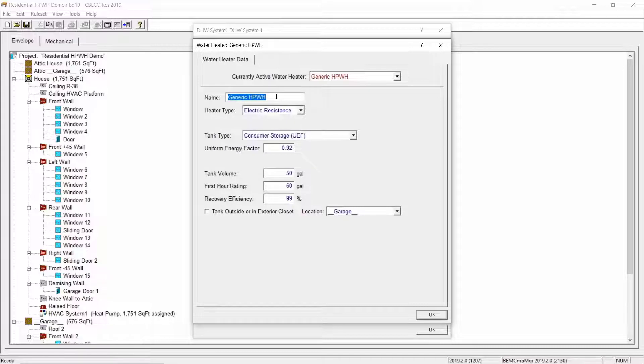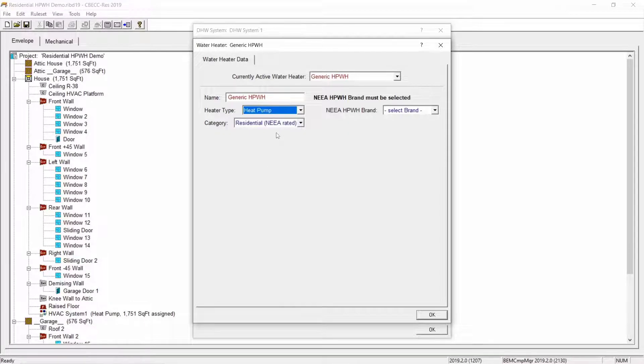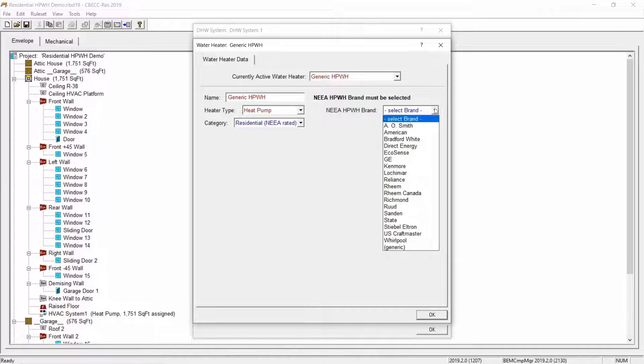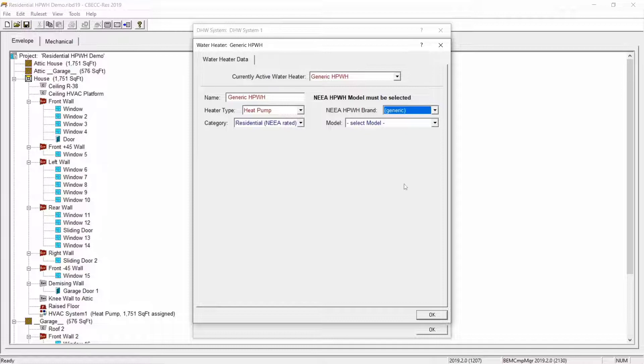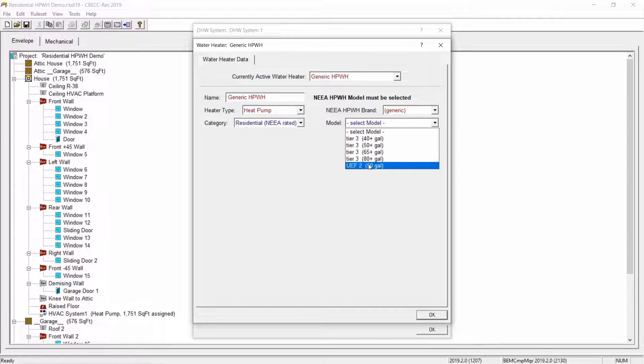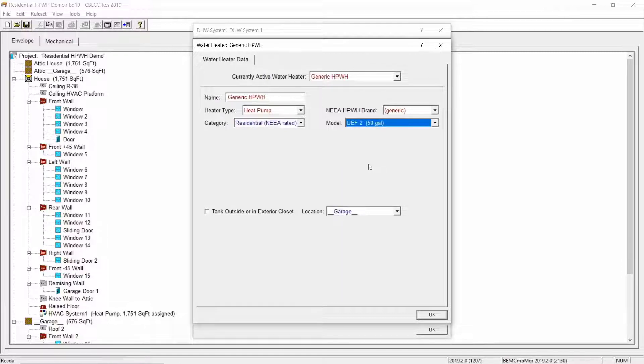This dialog box will allow us to configure the proposed DHW system to a heat pump water heater. Click the down arrow next to the heater type and select heat pump from the drop down menu. This will change the screen display to the heat pump water heater options. Next, click the down arrow next to the NEEA heat pump water heater brand input drop down and select generic from the list of water heater manufacturers. From the model drop down, select the UEF 2 50 gallon option. The water heater category drop down should already be set to residential NEEA rated, but if not, you can select it now.